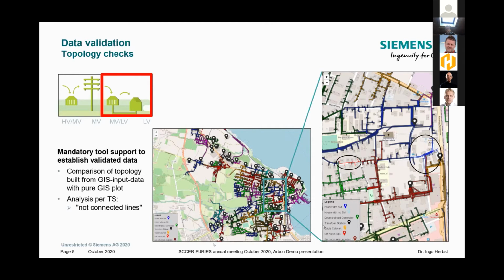First, on such an open-source map, the GIS data is put in as circles. Here you see just the GIS points, and then with black around it you see the second data coming from the topology builder. If a section isn't covered by the topology builder, it's obvious that somewhere there's a connection mismatch, so you can give a direct hint to whoever maintains the GIS database about where the problem is. With this graphic support it is very fast, and it helped enormously to debug the database, which was fine for its past purpose.